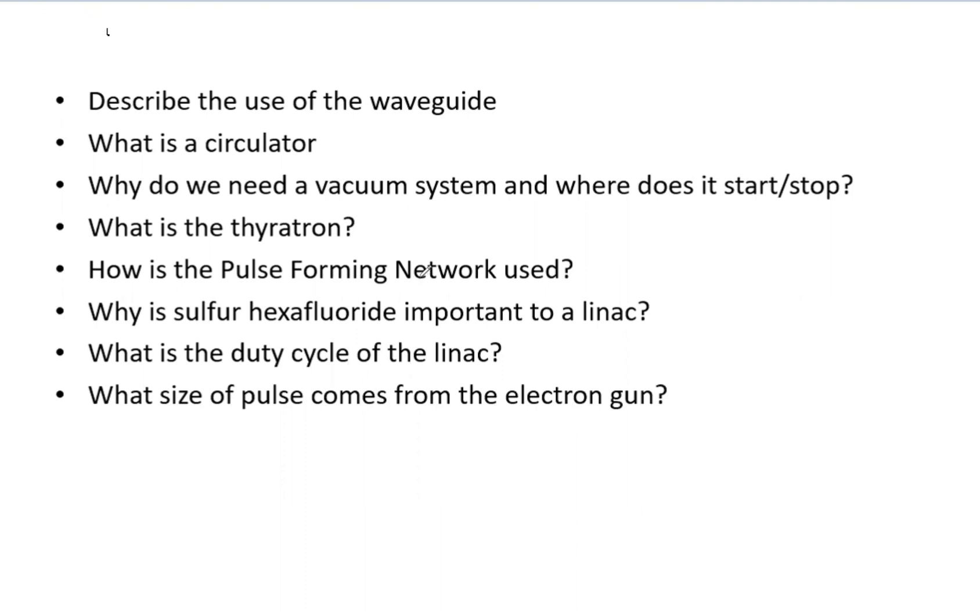Now why do we need a vacuum and where does it stop and start? So the electrons would collide and deflect with air and the electron gun would ultimately burn out. This is maintained by the ion pump.